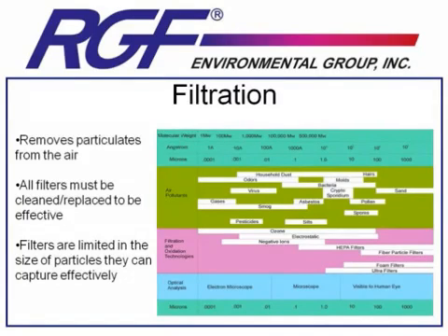Even if you look at HEPA filtration, the best available filter device, you're still only down to 0.1 microns, meaning that much of the viruses and bacteria and dust will not be captured by a HEPA filter. So filter devices are going to be limited to capturing particulates like dust, dander, and pollen in the air. They're largely ineffective on the microbe and gas category, including bacteria, viruses, mold spores, and odors.